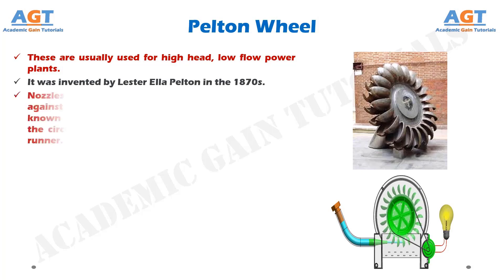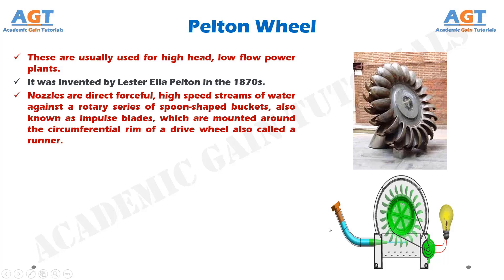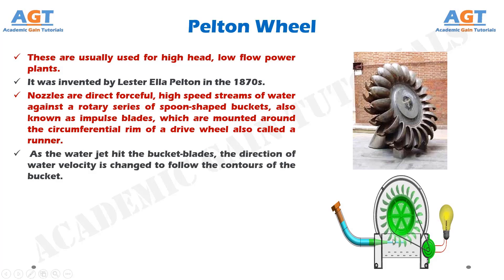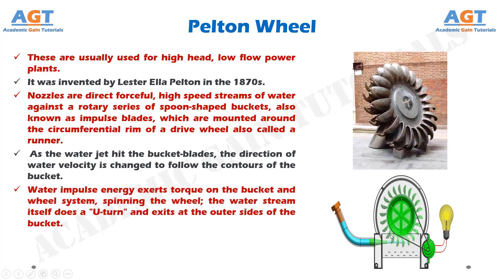Nozzles direct forceful, high speed streams of water against a rotary series of spoon shaped buckets, also known as impulse blades, which are mounted around the circumferential rim of a drive wheel also called a runner. As the water jet hits the bucket blades, the direction of water velocity is changed to follow the contours of the bucket. Water impulse energy exerts torque on the bucket and wheel system, spinning the wheel. The water stream itself does a U-turn and exits at the outer sides of the bucket.